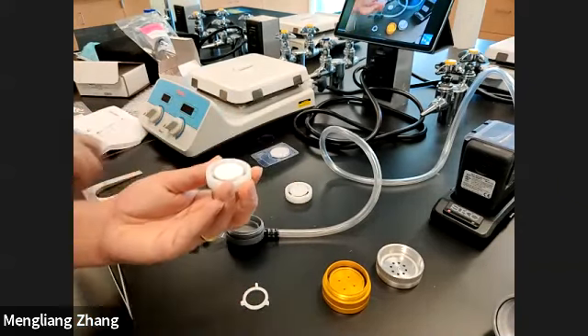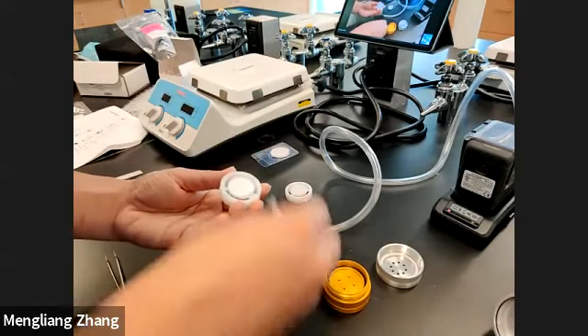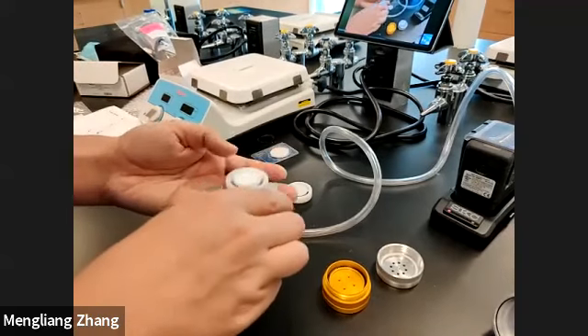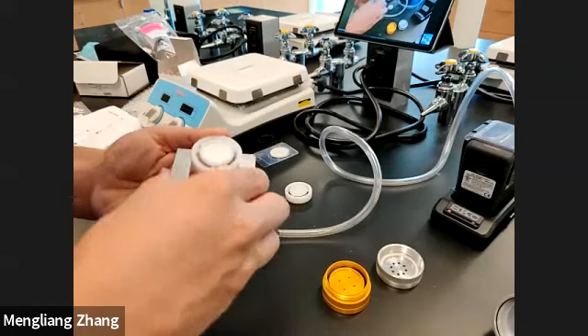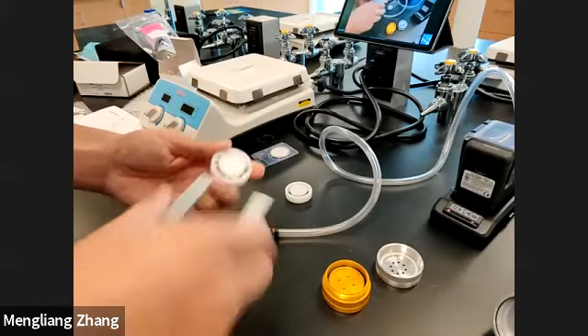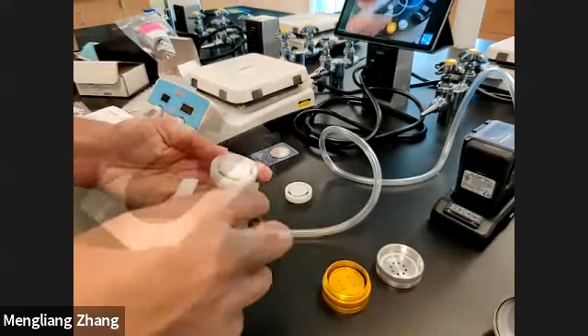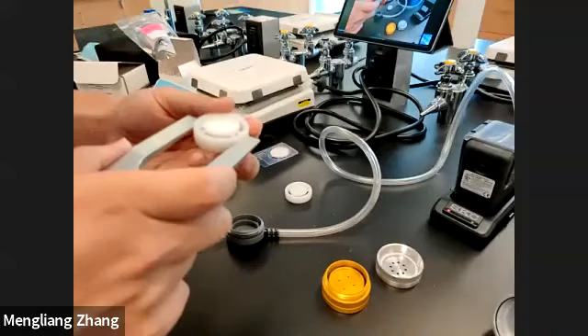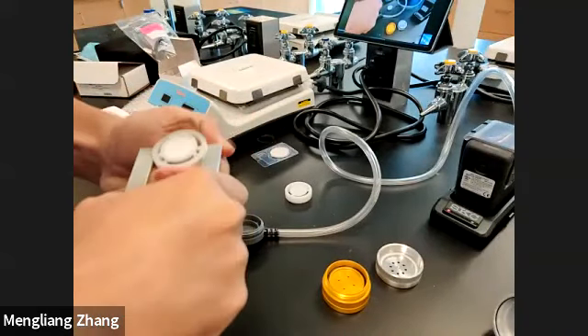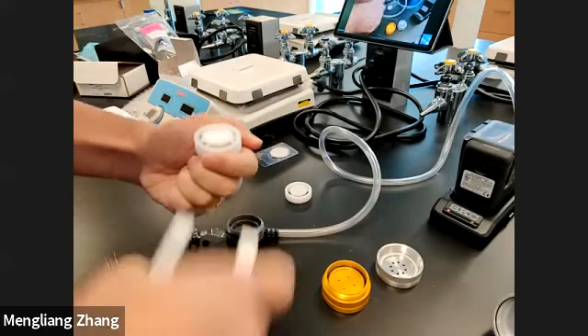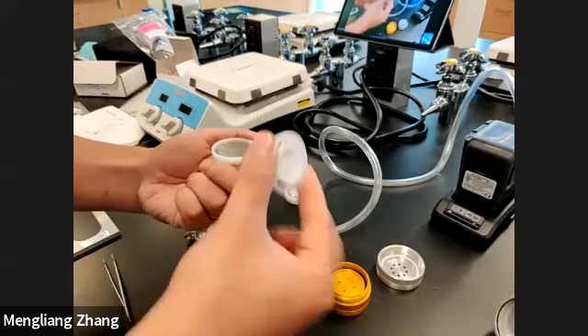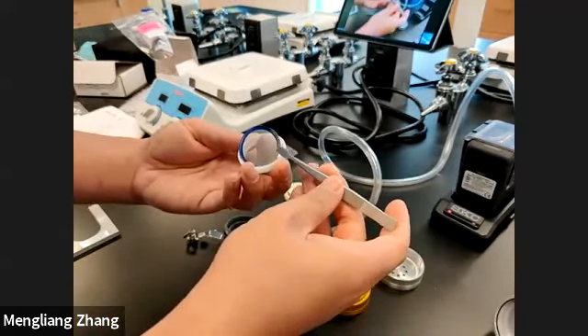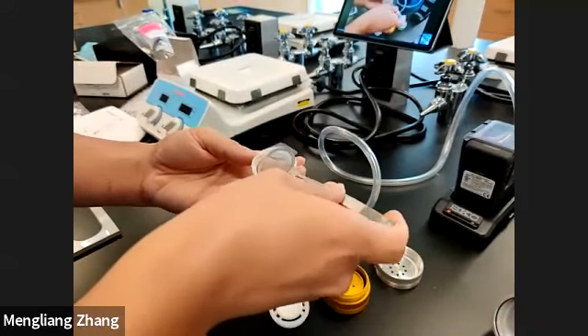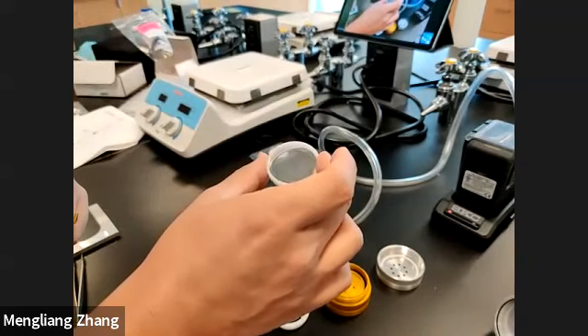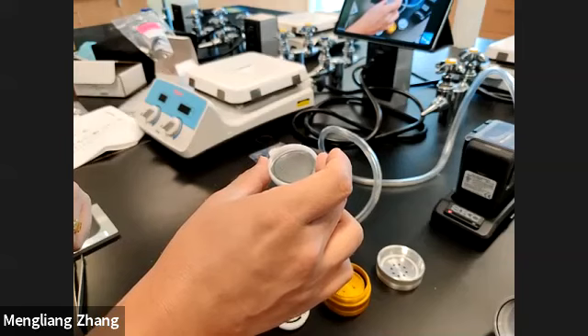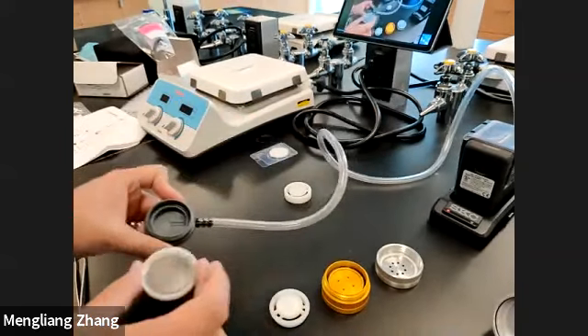Okay. And below this, let me put this back. Okay. Below this is the final filter, which is the 37 millimeter quartz filter in this study. We have this called a cassette opener. All you need is to insert this cassette opener into the side, and then you should be able to open this relatively easily. Okay, so then you take it out. You can see it's kind of a metal mesh. So it's just a support. So you put this back. On top of this metal mesh, we have to put a 37 millimeter quartz filter. Okay, so that's all the components of this impactor.